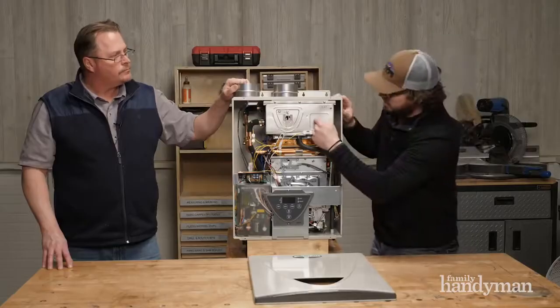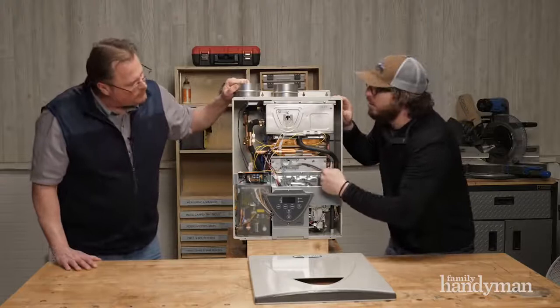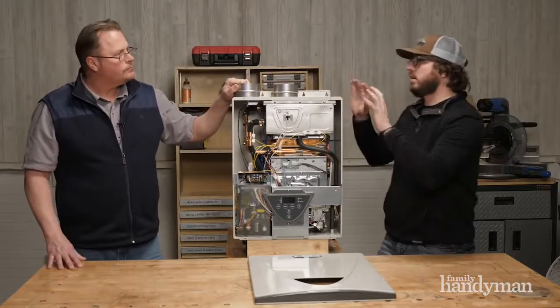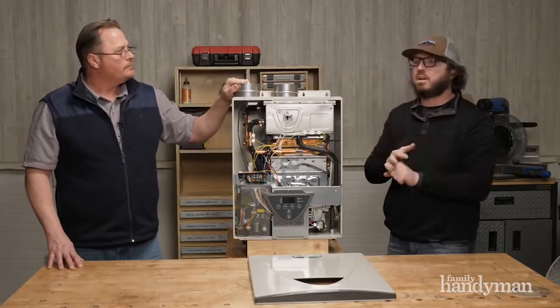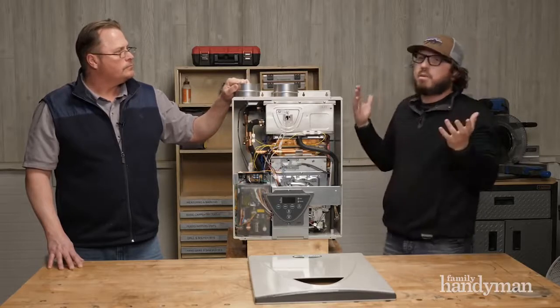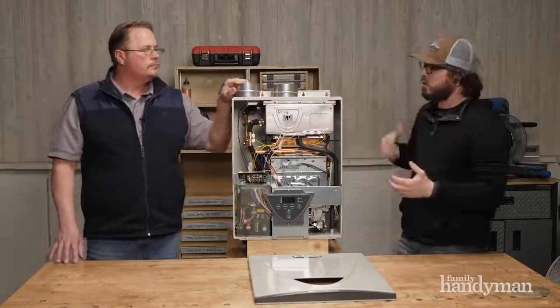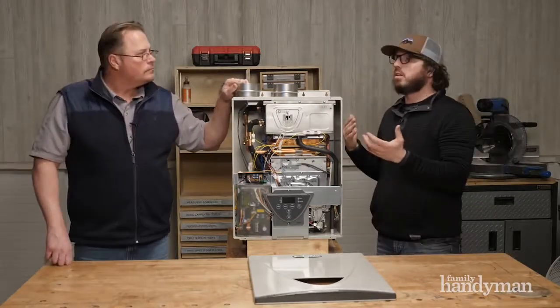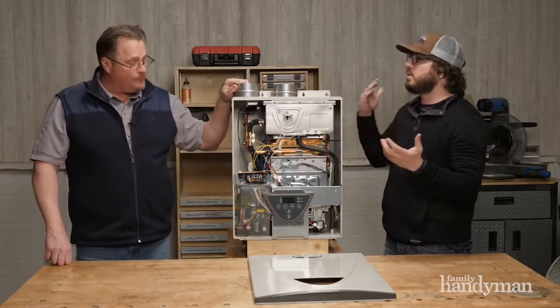A lot of stainless steel, a lot of copper, a lot of aluminum - there isn't rusting on the big parts, and that means longevity. So if you clean these, I recommend once a year at least, you flush these. If you keep flushing these, they'll last 25, 30 years - that's double a regular water heater.